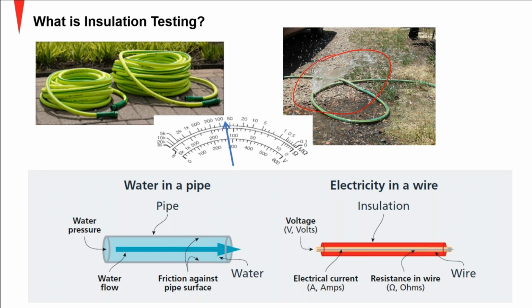So the same applies in electricity. The voltage basically equates to the water pressure, to the pressure that you apply. And ideally, you want current to circulate only through the conductor, so through the pipe. But if you have a defect, then that's going to leak somewhere there. And the same happens with the insulation. If you have this insulation deteriorated and it's connected to ground, then that is going to have some leakage there, and that's going to affect your installation. So that's what we are doing with the insulation. We're applying a voltage, and we want to determine if there's a leakage.